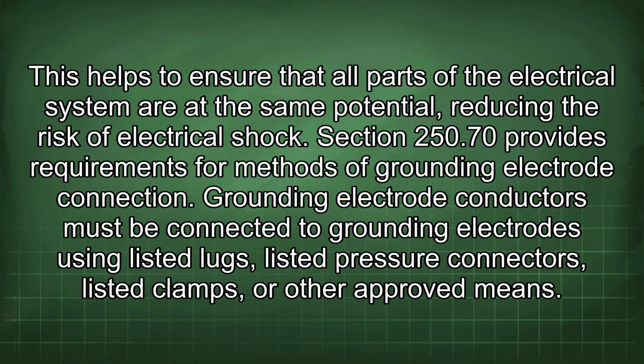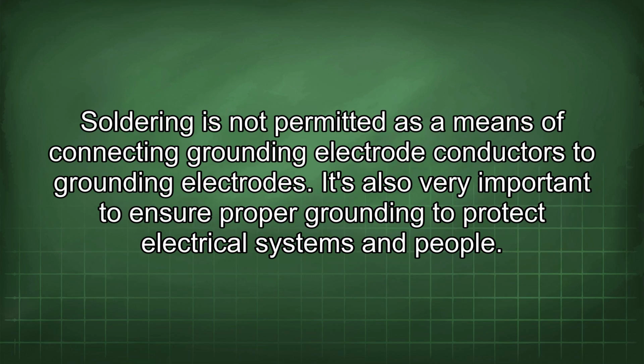Section 250.70 provides requirements for methods of grounding electrode connection. Grounding electrode conductors must be connected to grounding electrodes using listed lugs, listed pressure connectors, listed clamps, or other approved means. Soldering is not permitted as a means of connecting grounding electrode conductors to grounding electrodes.